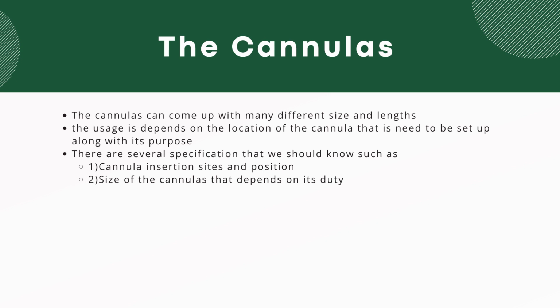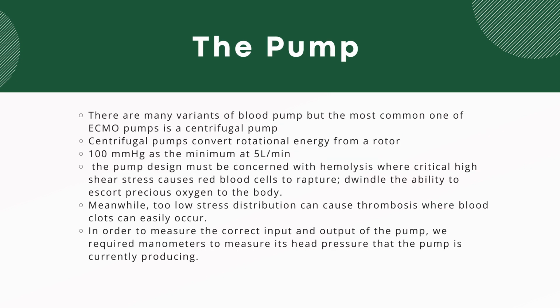The next one is the heart of the ECMO, the core that makes everything work. It is the pump. There are many various types of blood pump that exist today, but the most common one for ECMO is the centrifugal pump, which moves the blood by rotation. The centrifugal pump converts rotational energy from a rotor or impeller spinning between 2000 and 4000 rounds per minute, depending on the design, into kinetic energy of at least 100 millimeters of mercury as the minimum requirement of head pressure at 5 liters per minute.